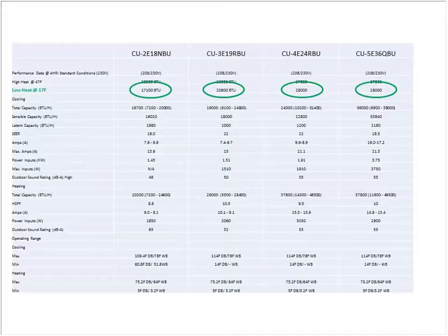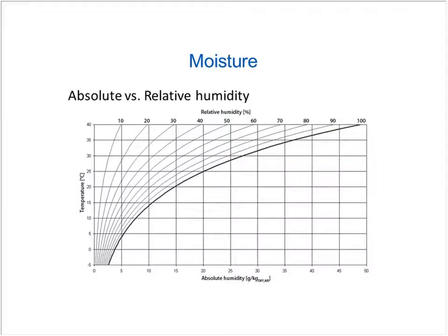Yeah. So next thing we do is we go to moisture, because one of the things we have to use caution with, and I don't know if many of you were on the AHRI that Jeff Klinowski did last week, but we talk about bringing fresh air in. The new codes require fresh air changes, mechanical air changes in the property, right? Which can bring in moisture, and it can actually exhaust moisture depending on where we are outside.